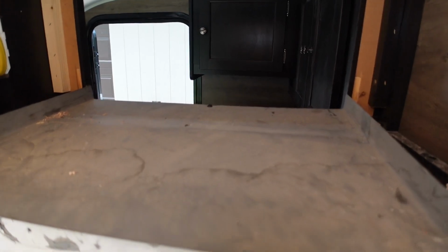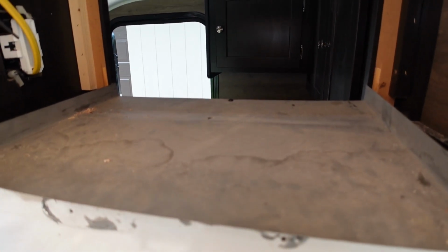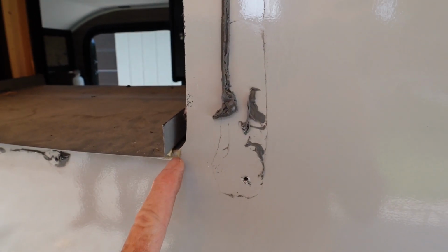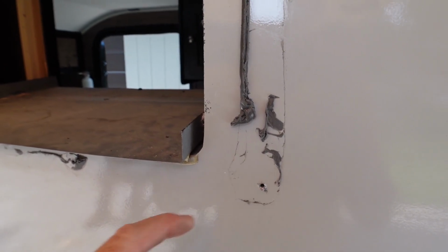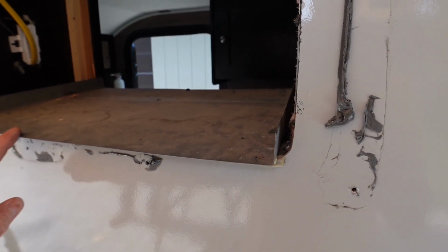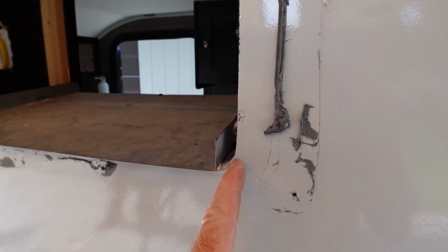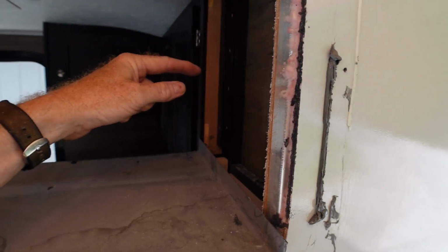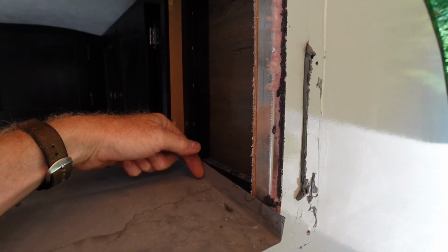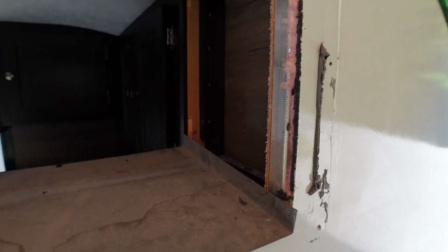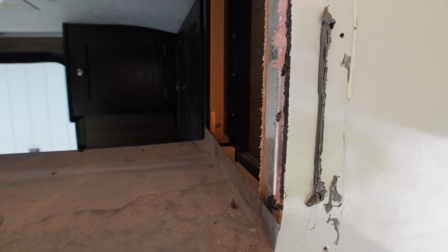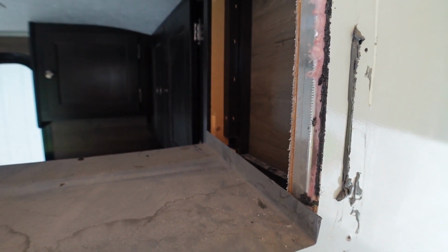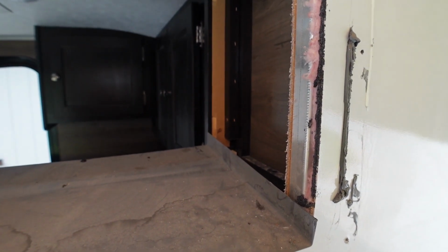So we got that removed now, and we're going to remove this pan. And what I'm going to do is, how these corners are rounded from where they cut them out, I'm going to square these corners up so that I have 2 square corners, and then we're going to rebend this pan so that it sits tight in these corners. Because what I want to do is create sides here on the inside of the opening, and I want them to come down and overlap this pan, and I want this opening to be as wide as I can have it so that I can get airflow in the sides to help get air into the compressor side of our air conditioner to help increase the efficiency and get it more air to work with.